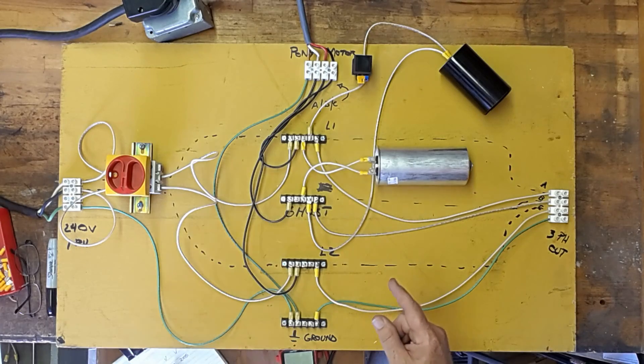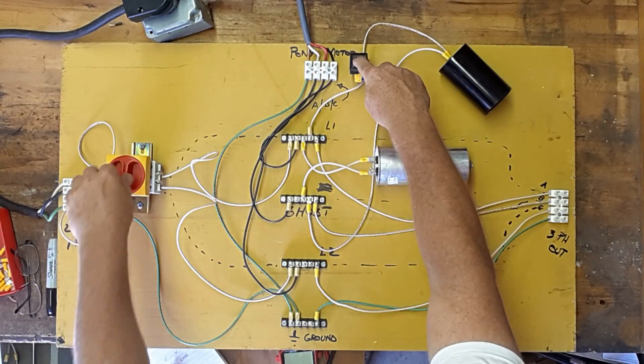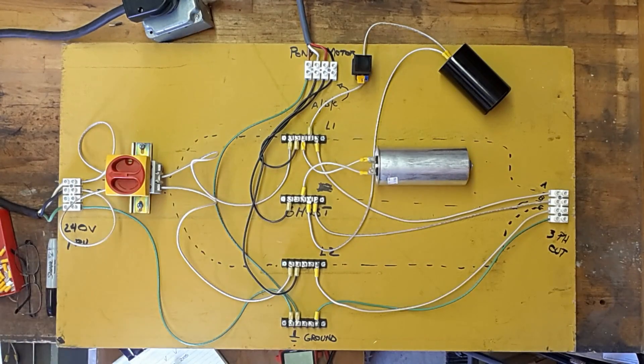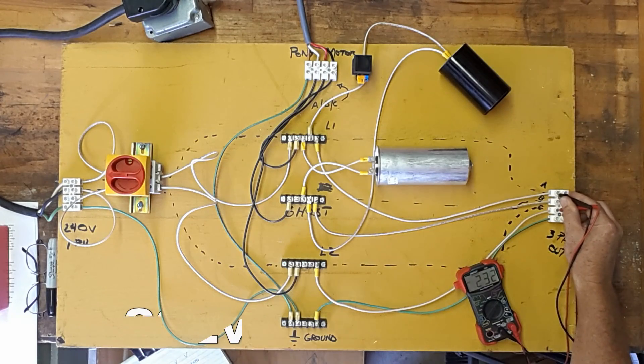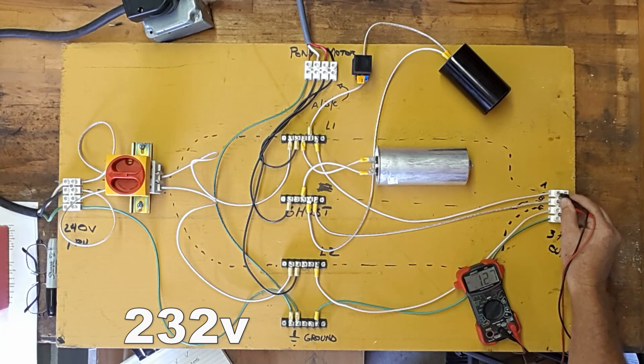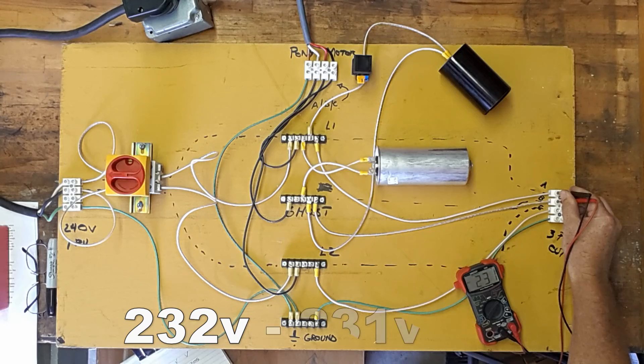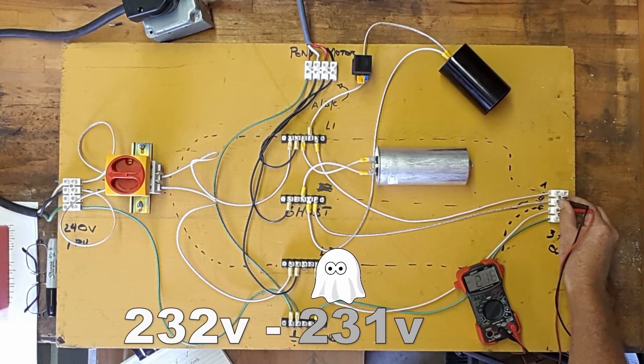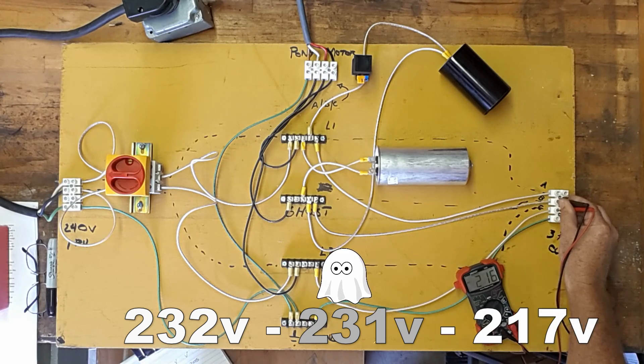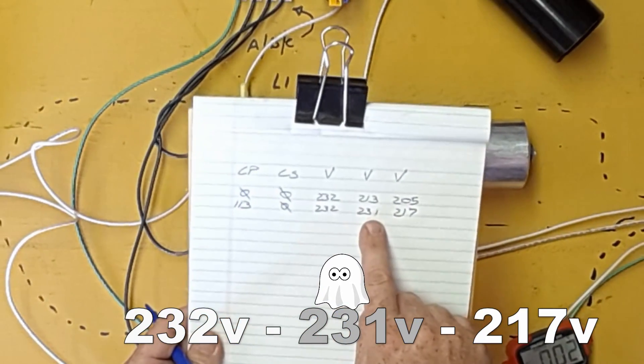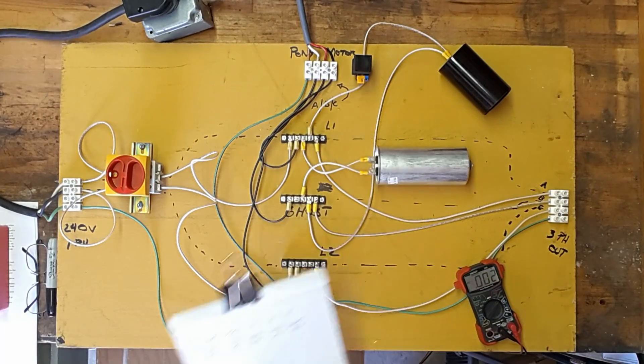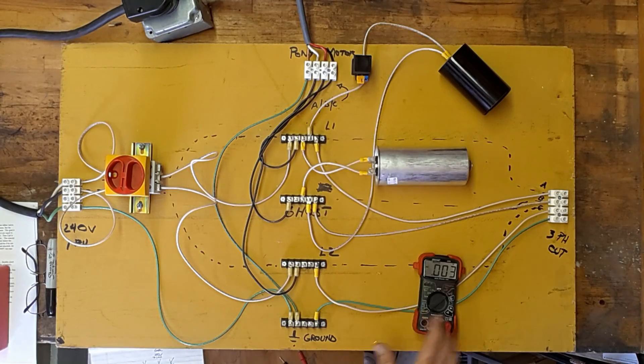With one capacitor in, listen how fast the motor starts now. Just with one. Just like that. Now this is where we notice there's a big jump here. And not much of a jump here. And that's to be expected. And that actually tells us which one of these letters is which.